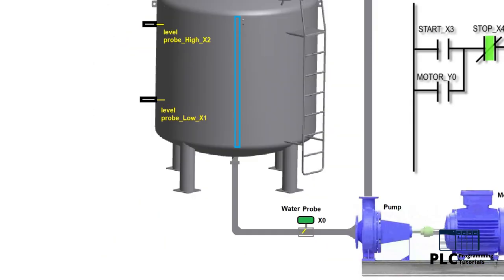This probe is used to detect the water inside the suction line. It will stop the pump if it detects no water in the suction pipe, thus preventing the pump from getting airlocked.